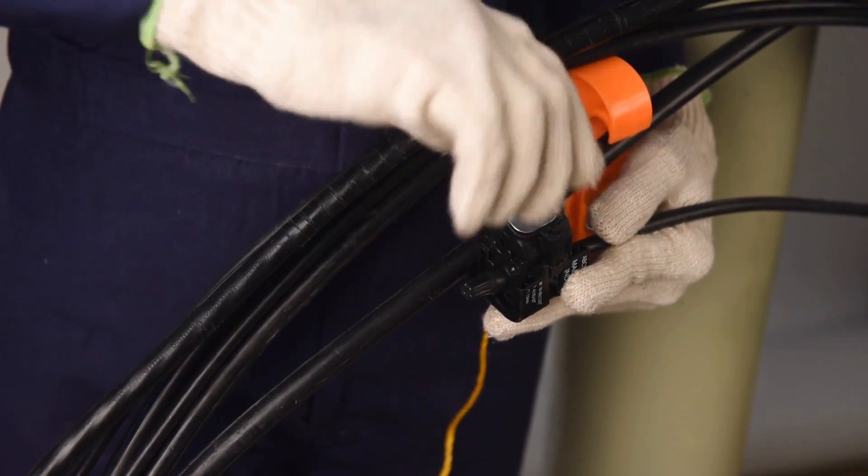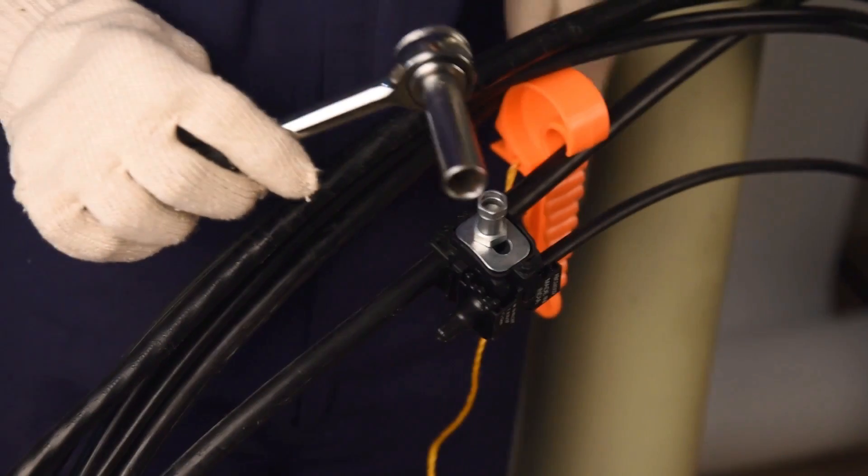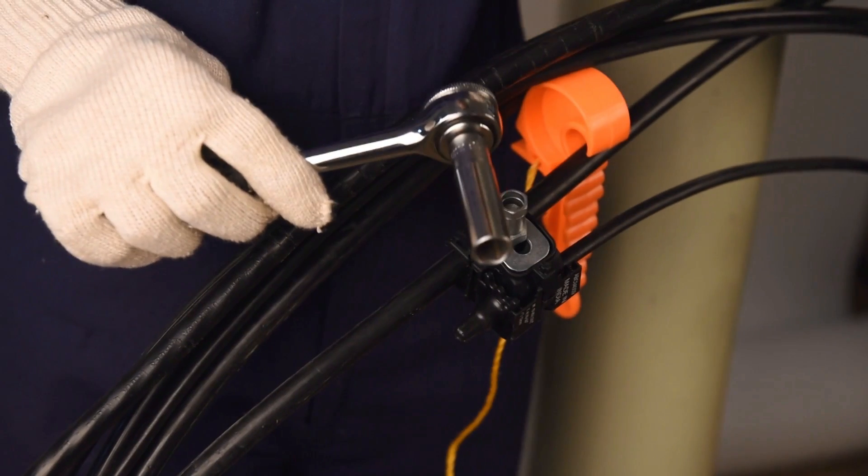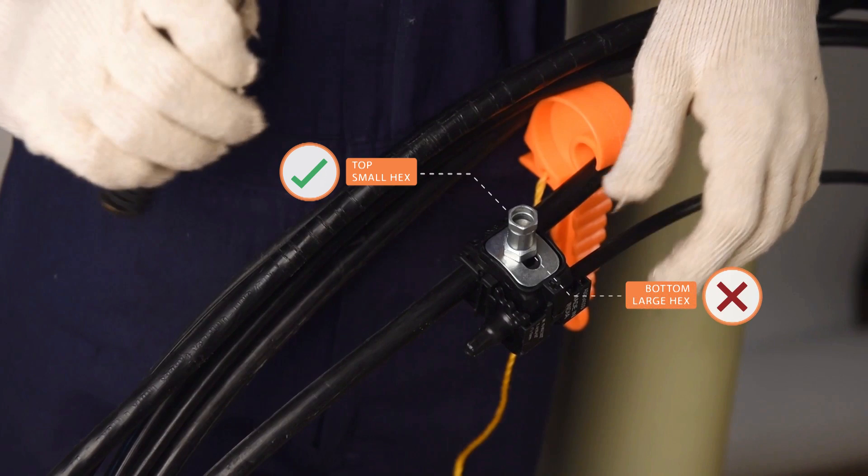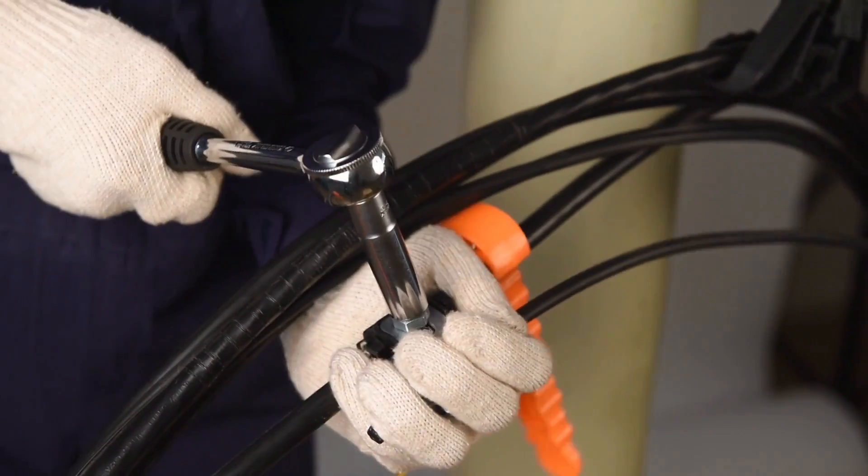Tighten the shear nut using the specified spanner size. Note: spanner size should be selected such that it fits with the top small hex and not the bottom large hex of the nut. Tighten the shear nut until the top small hex shears off.